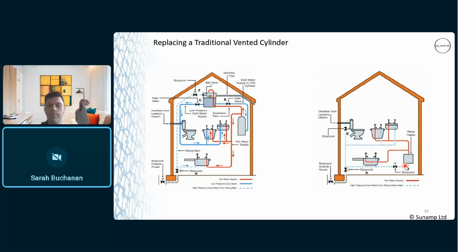Someone else has asked, if you fit the PRV on the property with a combi valve, as it has a check valve in it, wouldn't it need to be after the valve? With the combination valve, the expansion relief would be after the check valve anyway. So your pressure reducing valve is essentially your non-return valve in some cases, but the expansion relief would be after that within a combination valve.